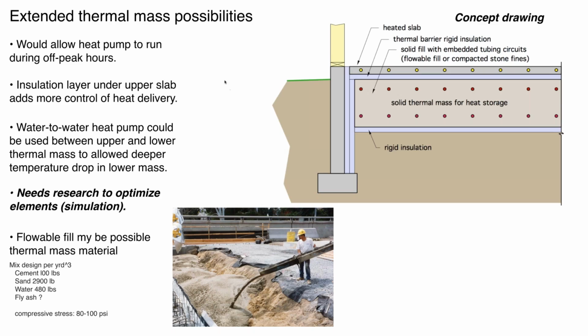Now, here's, I'll call it, a bit of a futuristic concept. If we look at this cross section up here, you'll see there's a heated slab and there's insulation. This light blue material would be insulation. But down below that is another larger area, and we call that a solid thermal mass. And the idea here is that we have tubing. Perhaps I'm showing 2 grids of tubing installed in this thermal mass.